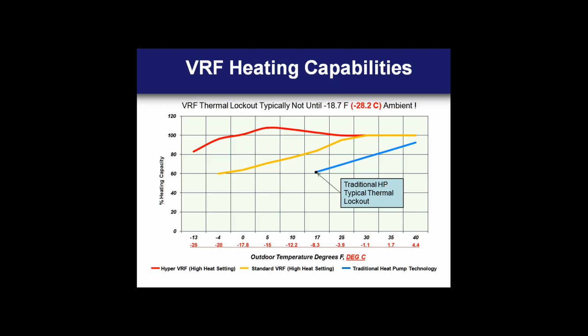In terms of heating capability, this is where VRF really brings in a large advantage when comparing it to conventional air source heat pumps, and that's really represented by that line on the left, that blue-colored line. You'll typically see derates close to 60% at around minus 8.3 degrees Celsius, and that's typically a lockout condition. These curves on the left represent VRF technology, and it varies depending on the make and manufacturer.